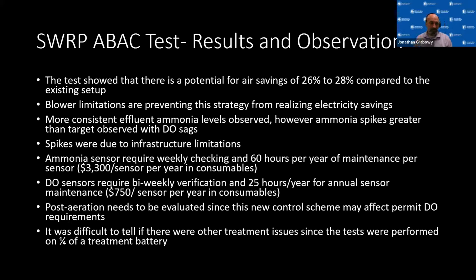I saw some people were asking about cost of sensors and stuff like that. Sensors are expensive to maintain. Each ammonia sensor requires weekly checking and 60 hours per year of maintenance per sensor. And if you have 2 sensors per tank and we have eight tanks per battery and we have 4 batteries, that adds up really quick for our Stickney plant. The DO sensors, conversely, are a lot less expensive. They're 25 hours a year for annual maintenance and $750 a year in consumables. So even if they are reliable, you have to really stay on them to make sure that you're getting good data and your system's making good decisions with it.